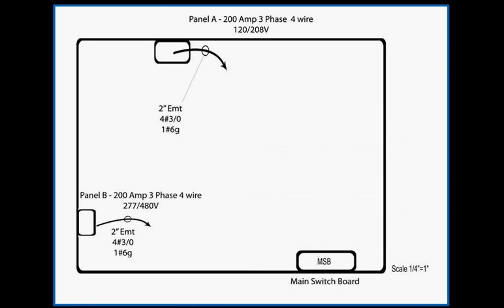The drawing shows a top view of a building containing three electrical panels. It also shows feeder conduit, which runs from the main switchboard MSB to both panels, A and B. Both panels are 200 amp, and both panels are fed with 2-inch EMT with four 3-Aught copper conductors and one number 6 ground. I will demonstrate how to take off 2-inch conduits feeding both panels and transfer the information to Red Rhino.